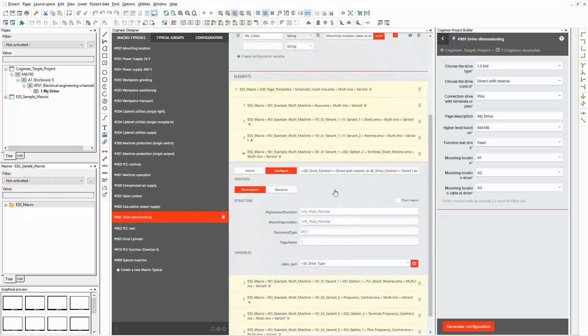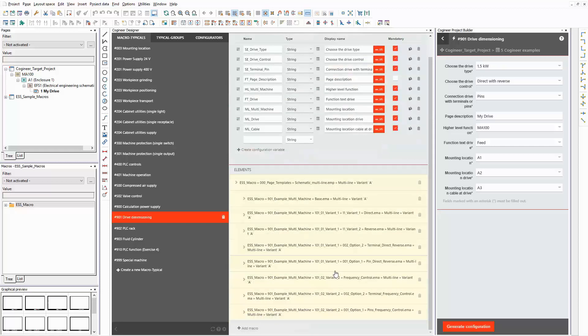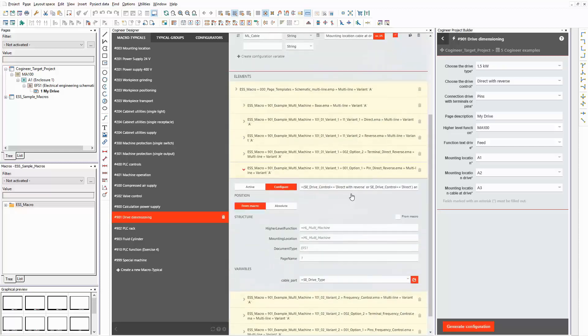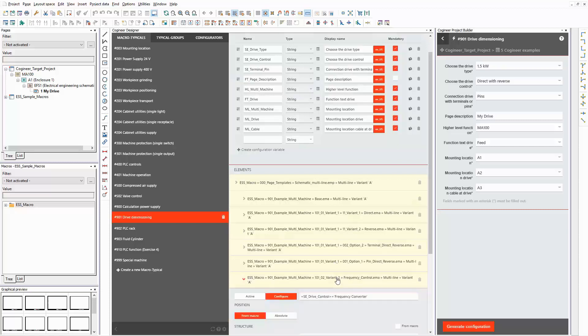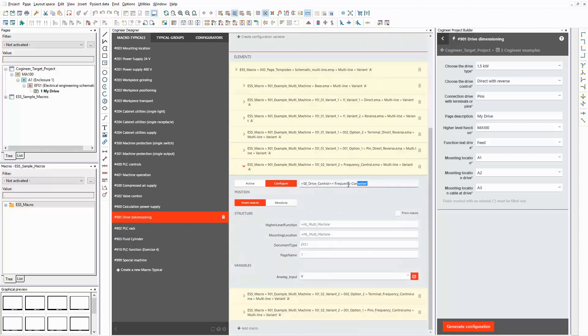The fourth macro contains the partial circuit for the option 'direct with reverse'. It is used only if the related option is selected. The following two macros contain the partial circuits for the connection types. They are used in combination with the direct with reverse or direct drive control. The first one is used if the option 'terminals' is selected. The second one is used for the same drive controls, but only if the option 'pins' is selected. The next macro contains the partial circuit for the option 'frequency converter'. It is used only if the related option is selected.